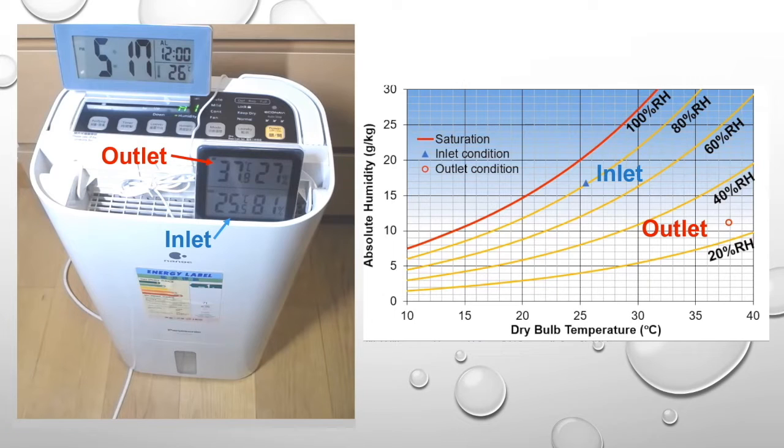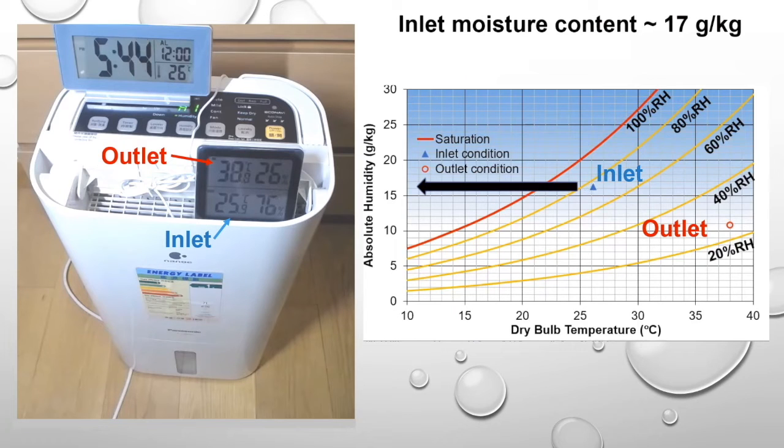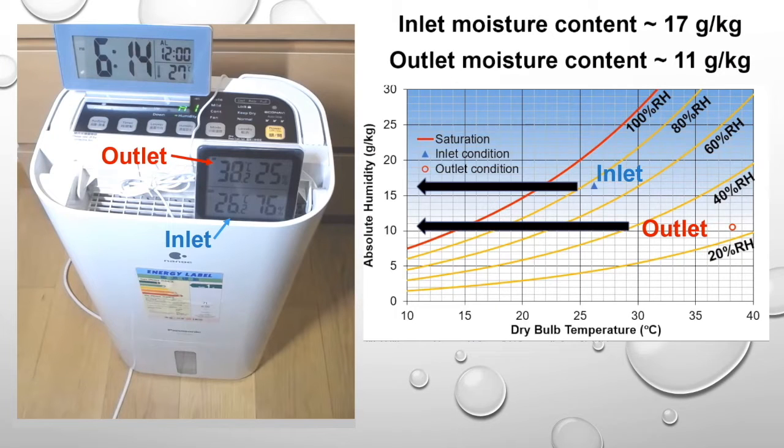We know that the dehumidifier is functioning because the inlet temperature is about 26 degrees Celsius with a relative humidity of about 80%, corresponding to a moisture content of about 17 g per kg, whereas the outlet temperature is about 38 degrees Celsius with a relative humidity of about 25%, corresponding to a moisture content of about 11 g per kg. So the moisture content of the outlet is lower than that of the inlet.